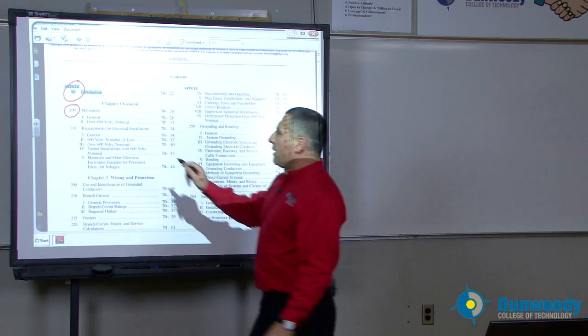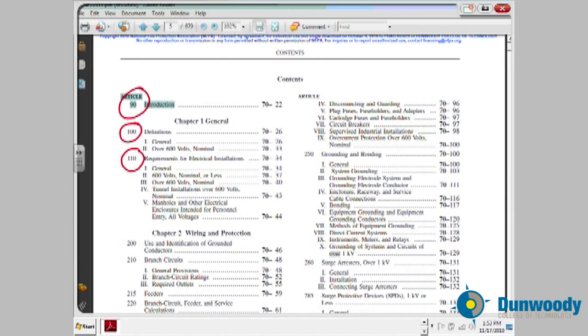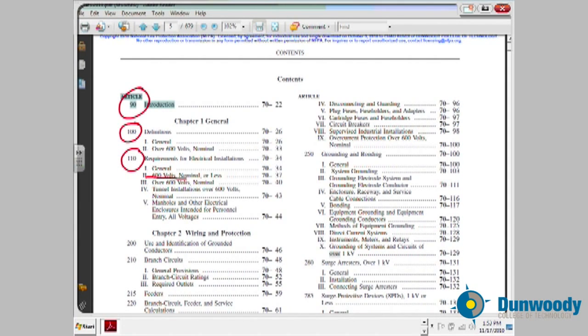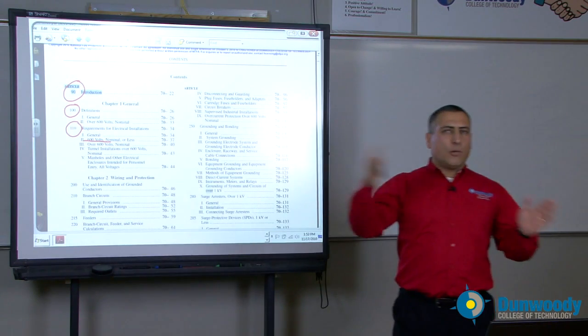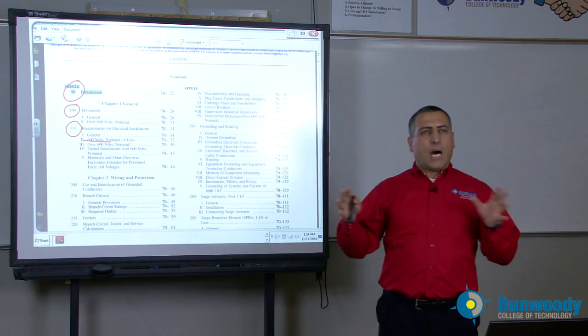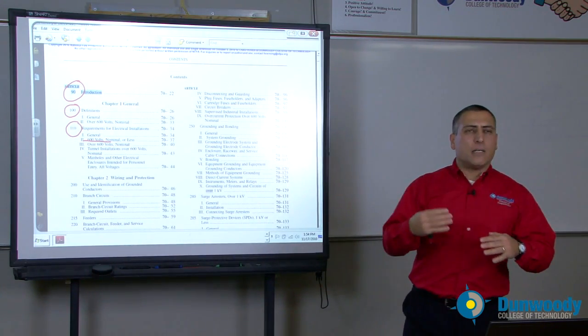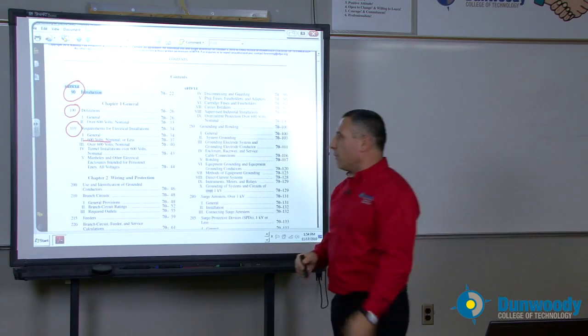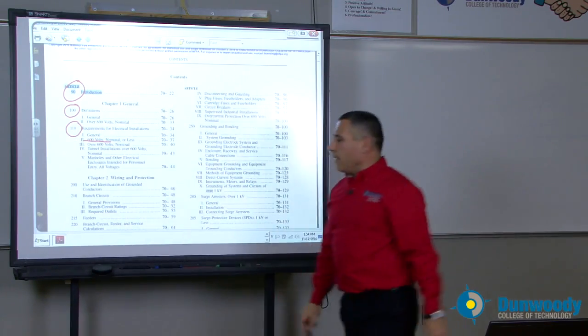Another very important topic is requirements for electrical installation. As you can see from the table of contents, if you are dealing with anything 600 volts or less there are certain requirements; for high voltage there are other requirements. This covers how to install electrical equipment — for example, how far you need to keep clearances in front of a 4,000-amp switchgear for an electrician to work safely, and dedicated space requirements for conduit runs into the system.